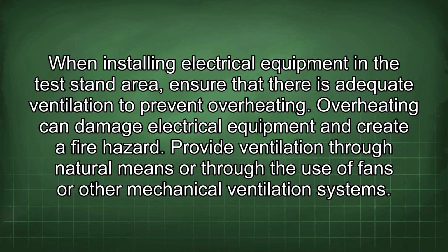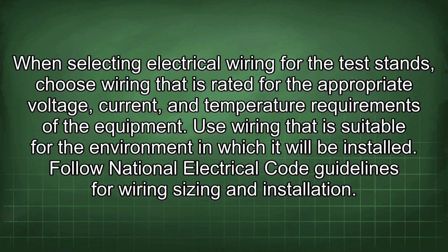When installing electrical equipment in the test stand area, ensure that there is adequate ventilation to prevent overheating. Overheating can damage electrical equipment and create a fire hazard. Provide ventilation through natural means or through the use of fans or other mechanical ventilation systems. When selecting electrical wiring for the test stands, choose wiring that is rated for the appropriate voltage, current, and temperature requirements of the equipment. Use wiring that is suitable for the environment in which it will be installed. Follow National Electrical Code guidelines for wiring sizing and installation.